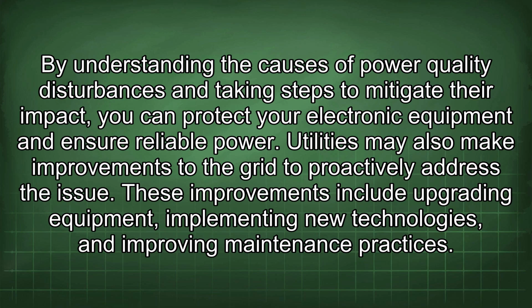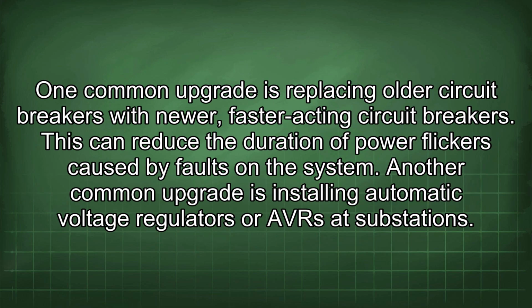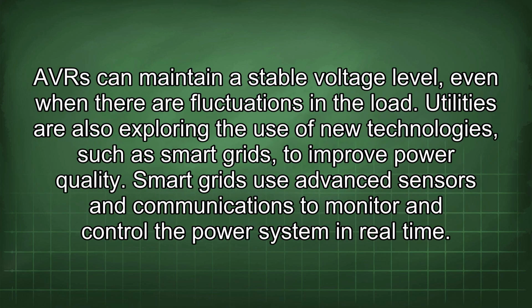Utilities may also make improvements to the grid to proactively address the issue. These improvements include upgrading equipment, implementing new technologies, and improving maintenance practices. One common upgrade is replacing older circuit breakers with newer, faster-acting circuit breakers. This can reduce the duration of power flickers caused by faults in the system. Another common upgrade is installing automatic voltage regulators, or AVR, at substations. AVR can maintain a stable voltage level, even when there are fluctuations in the load.